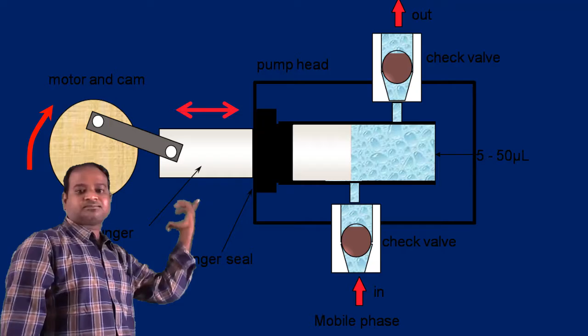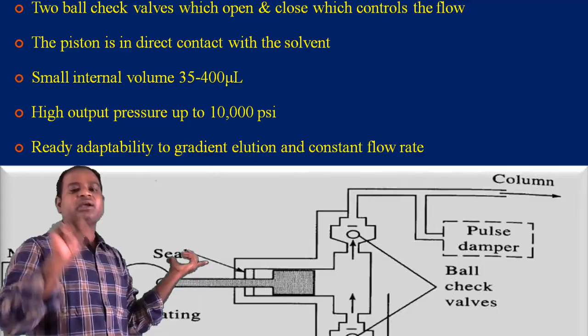Two ball check valves open and close, which controls the flow. The piston is in direct contact with the solvent. That is, it is sending solvent by alternative pressure. Small internal volume, 35 to 400 microliters, is present. High output pressure up to 10,000 psi. This is the main important point, that it can give us pressure up to 10,000 psi. Readily adaptable to gradient elution, and constant flow rate is present, but in some conditions it will give a pulsed flow, which can be rectified.